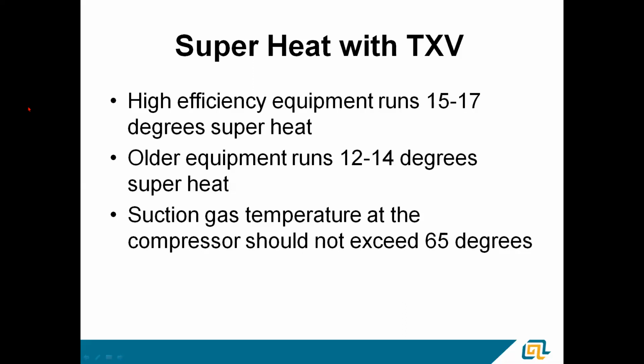Remember that a TXV is looking at the suction line temperature at the evaporator. It's very typical that you're going to heat up that superheated vapor as it passes through the line set, gets to that outdoor unit. That's why I say you really shouldn't see anything greater than a 20-degree superheat at the compressor. If you're really, really looking for an accurate superheat, measure it as close to the indoor coil as you possibly can. Suction gas temperature, again, should not exceed 65 degrees.